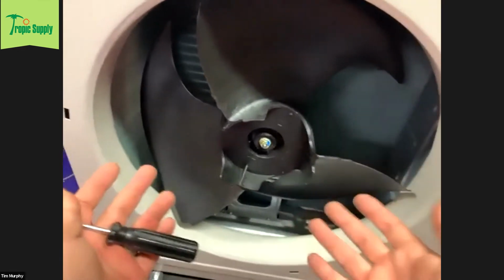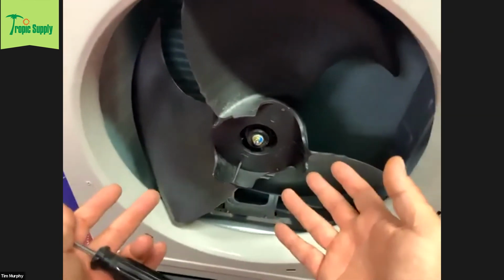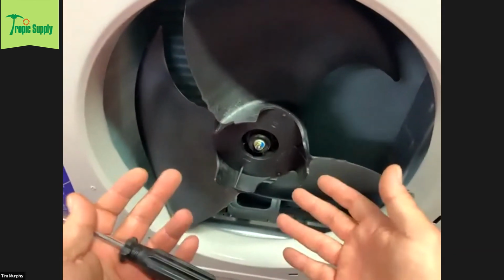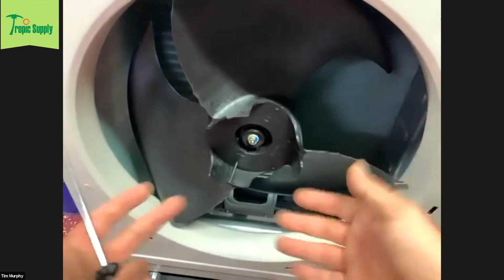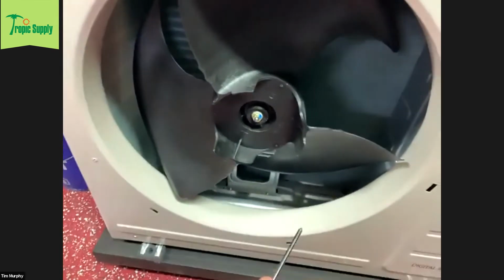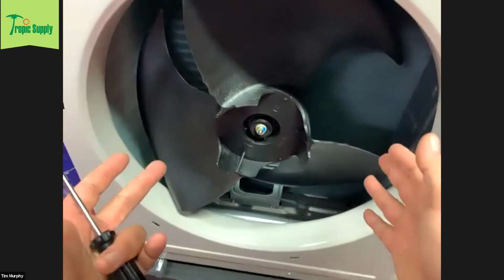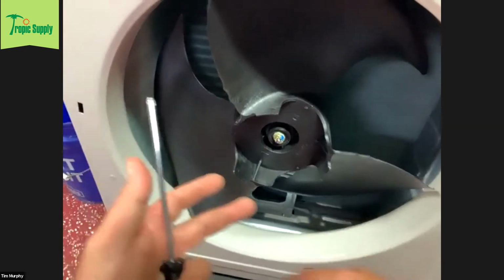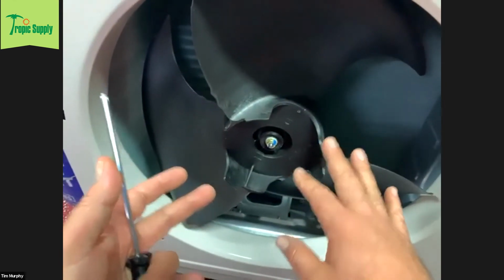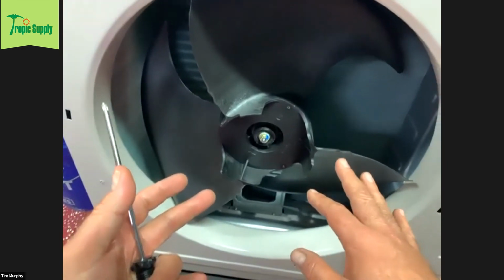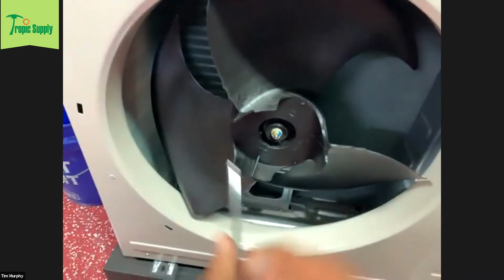As you can see, these are plastic, so you're really not going to be able to get a puller on it. If you can't get it off, chances are you're just going to order another fan blade and a fan motor. But in my experience with mini split systems in general, very rarely have I had to change a fan blade or a fan motor. So that's a good thing.